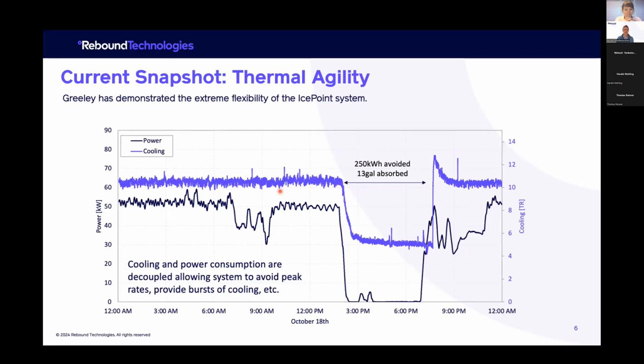Here we're supplying cooling and consuming power, and this is the peak window where we drop our power consumption to zero, but we continue to provide not only cooling, which is important, but even more important for the customers, moisture control, during a period where you're trying to turn down the system.